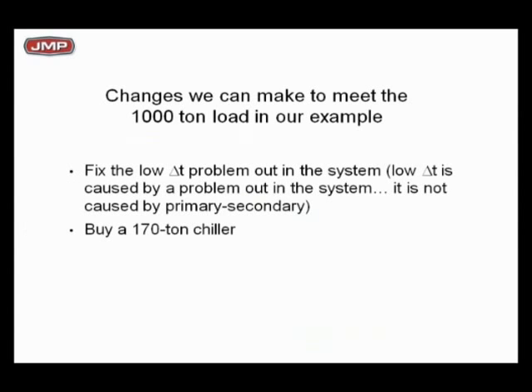So let's take a little bit of a look at this. How can we fix the problem? First thing to do is fix that low delta T problem out in the system. If you can fix it, get the 56 degrees back up, you're going to win. You're going to save energy. You've got plenty of chiller capacity. You're going to be able to get 1,000 tons.